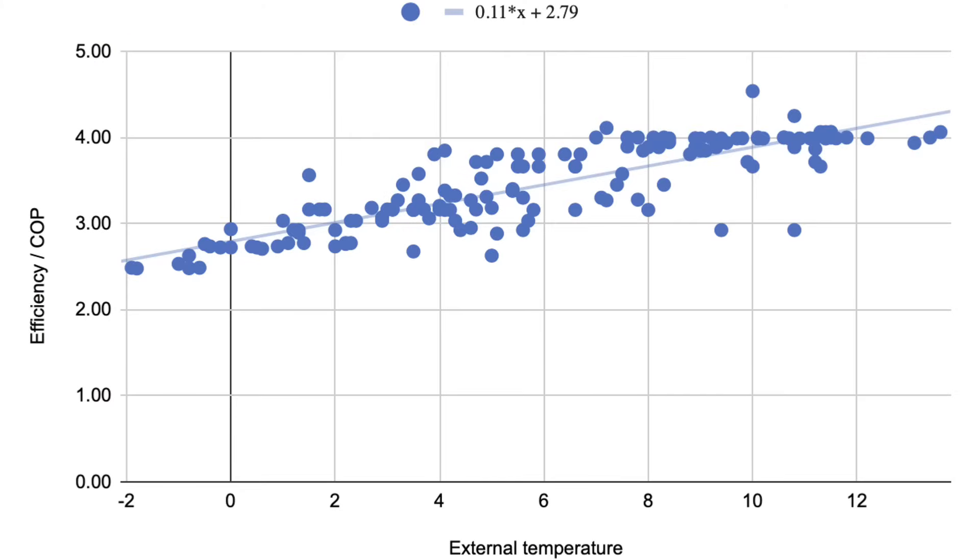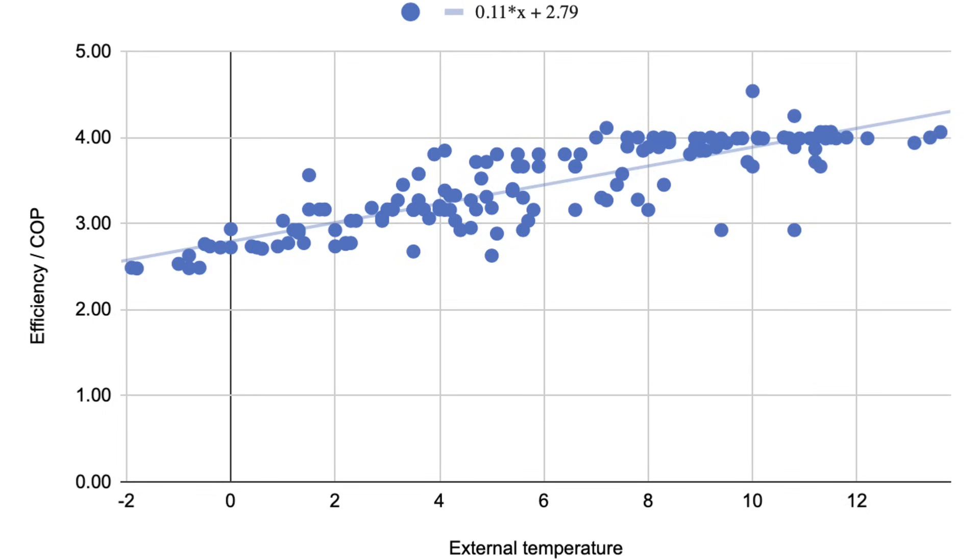Let's get even deeper into the stats. I've got lots of data for the last couple of years, and plotting daily heat pump efficiency against daily average temperature, I can plot a graph that helps estimate heat pump efficiency at different external temperatures. The data has a trend line with the equation Y = 0.11x + 2.79, which means at 0 degrees outside we'd expect a COP of 2.78; at 5 degrees, 3.33; at 10 degrees, 3.88. External temperatures do have an impact on heat pump efficiency, so you could try to estimate average performance for a similar system at your temperatures.